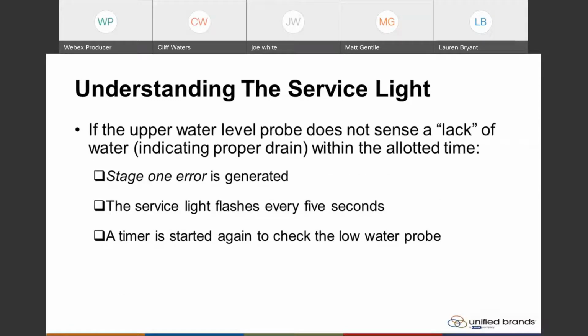If your upper water probe does not sense the lack of water, right, that stage 1 error is generated, the service light flashes every 5 seconds. A timer starts again to check the low probe. So now it's just going back, checking the low probe to verify it's reading or not, and then we'll continue with operation, or we'll give you that service light.